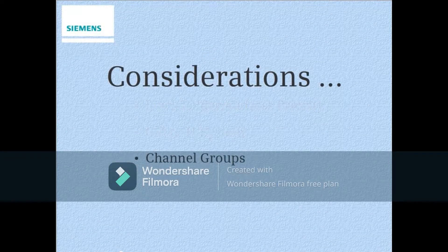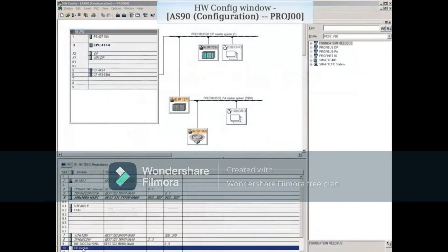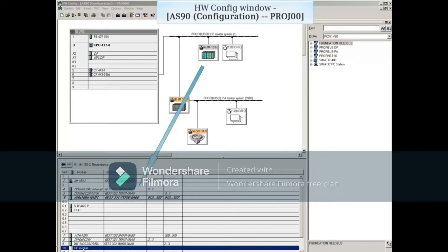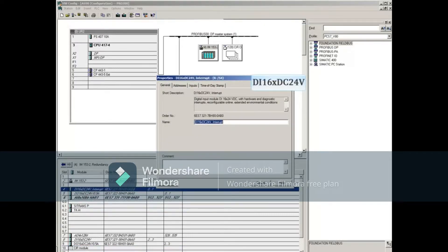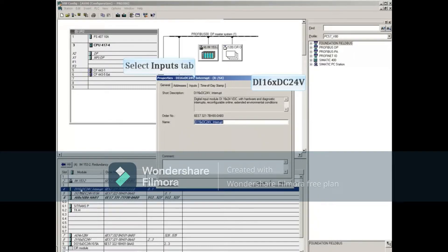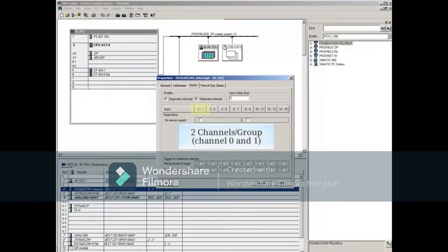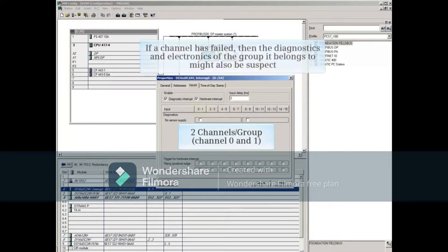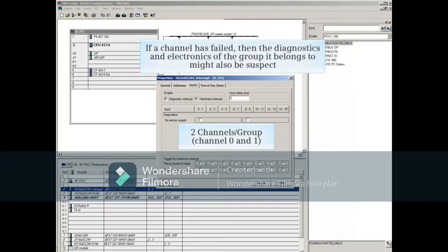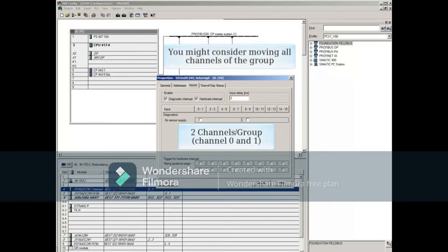Let's also consider if the channel you're planning to move is part of a diagnostic group. In this example, we'll plan on moving one of the field devices from a failed channel on the first DI module. If we double-click the module to open it, and select the inputs tab, we'll see that each channel is part of a two-channel group. If a channel has failed, then the diagnostics and electronics of the group it belongs to might also be suspect. You might consider moving all channels of the group. Cancel out of the properties window.